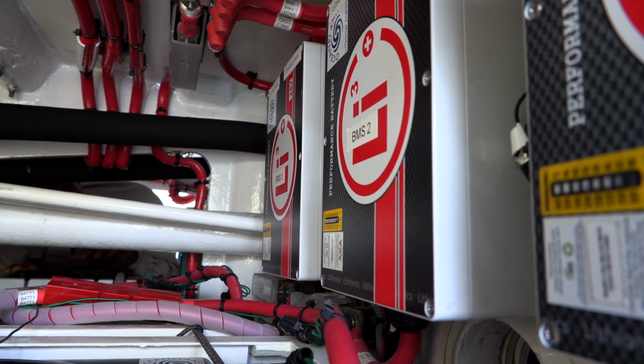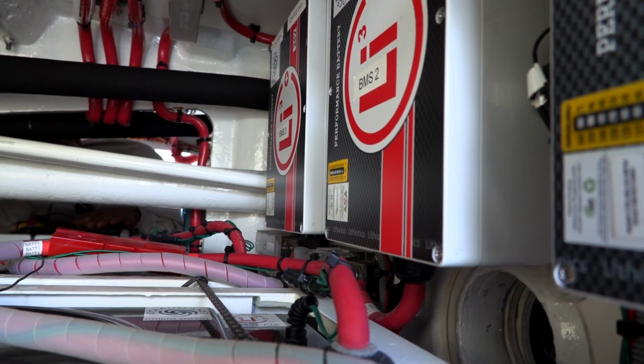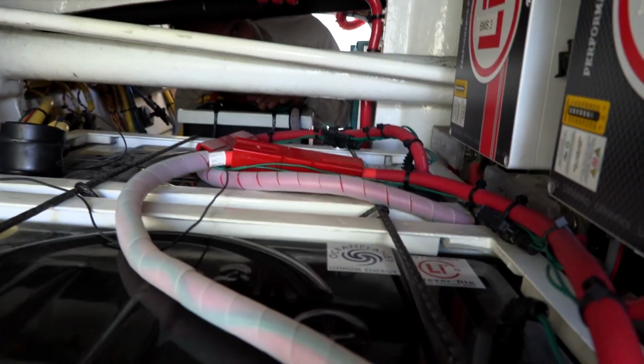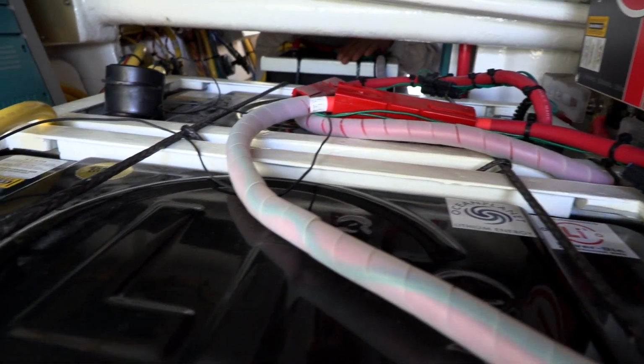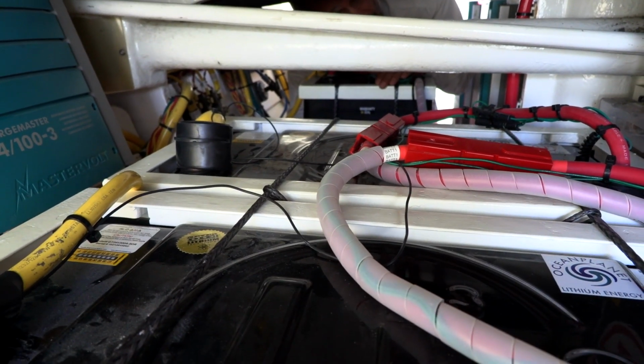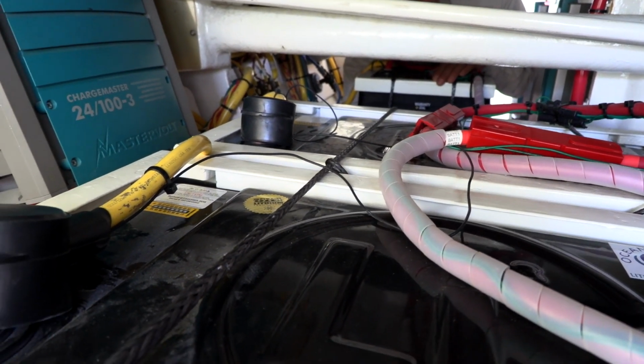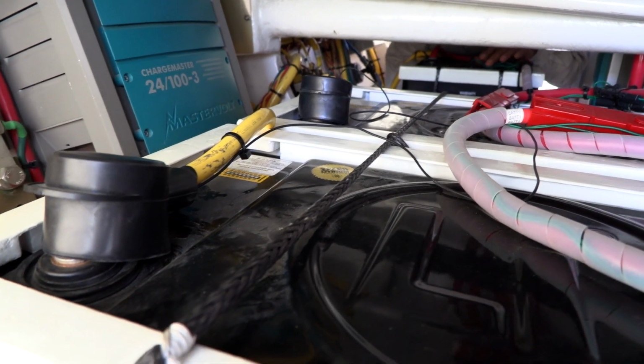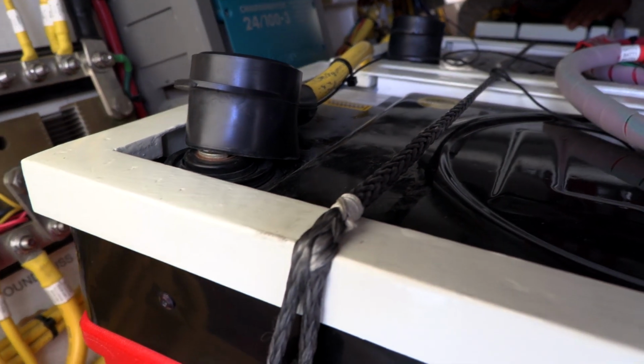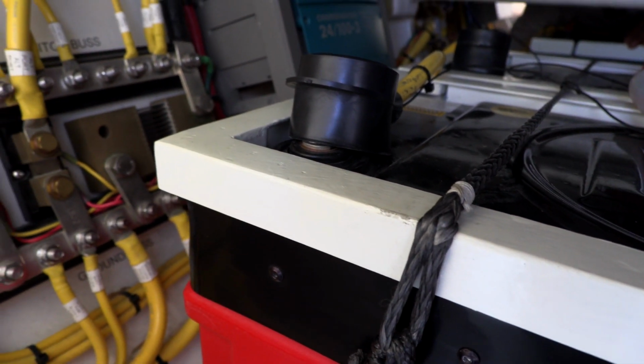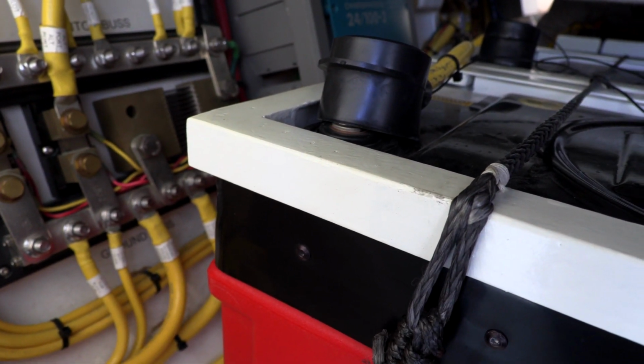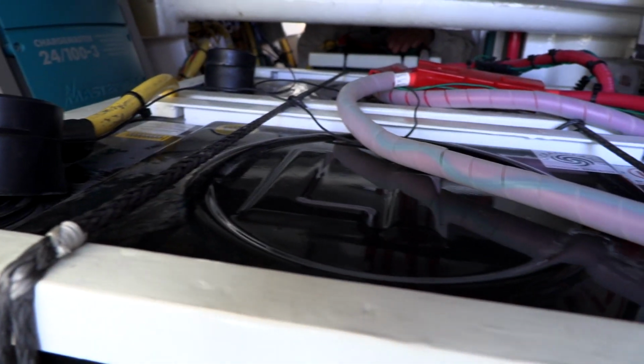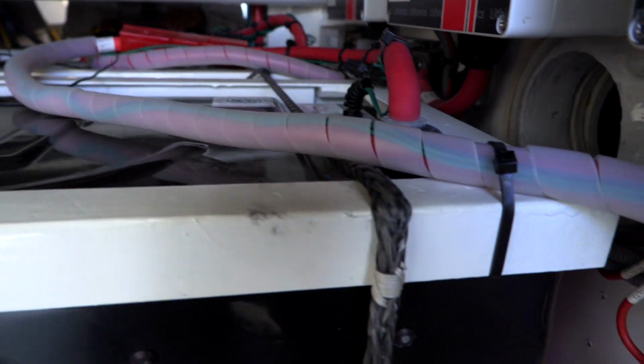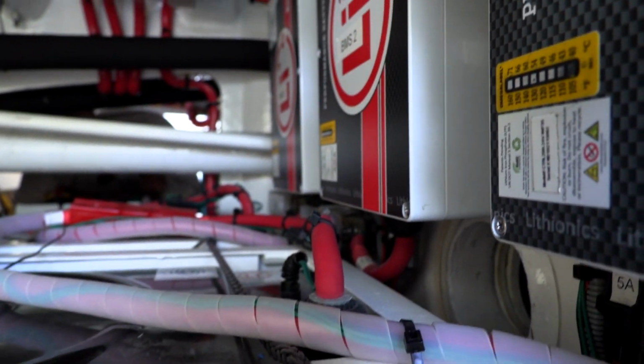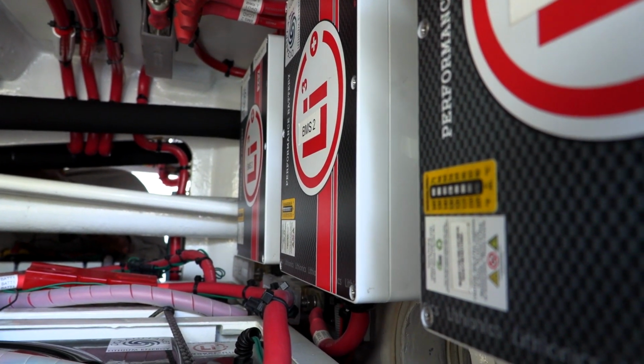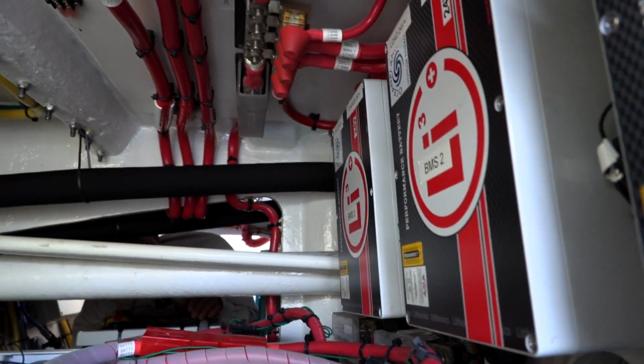So there are 3 banks in here. Each one is 300 amp hours at 25 volts, so it's a 900 amp hour system in this boat, which is a considerable amount of power — I think it's like 22 kilowatt hours. Each bank is independent, but they're all running in parallel, so it operates as if it's one 900 amp hour bank. However, if any one of them went offline, the other 2 won't be affected.